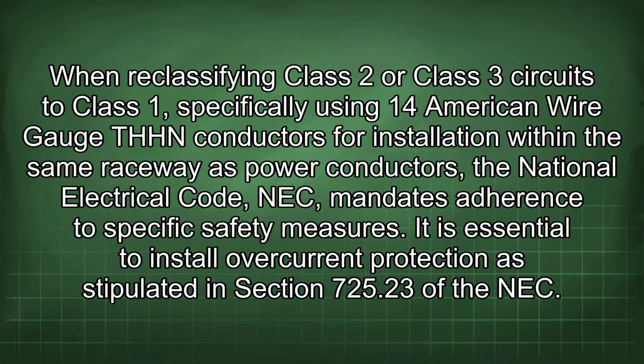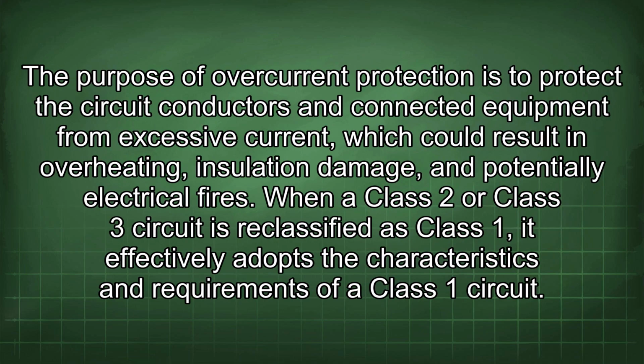When reclassifying Class 2 or Class 3 circuits to Class 1, specifically using 14 American wire gauge THHN conductors for installation within the same raceway as power conductors, the National Electrical Code (NEC) mandates adherence to specific safety measures. It is essential to install overcurrent protection as stipulated in Section 725.23 of the NEC. The purpose of overcurrent protection is to protect the circuit conductors and connected equipment from excessive current, which could result in overheating, insulation damage, and potentially electrical fires.